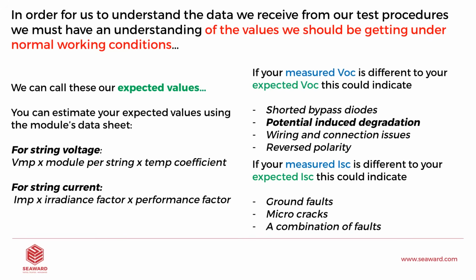So I mentioned briefly earlier that we can compare our measured values to our expected values, and this will give us an indication of what is wrong with the system. So for instance, if I go to a site and I'm dealing with this string, just to give you some arbitrary numbers, each panel is 40 volts VOC. There are 10 of these panels, so I should really see approximately 400 volts from this string. If I go to my test and I see 300, or I see less, or I see more, then that system isn't wired correctly, or maybe we have connection issues, maybe there is a shorted bypass diode.